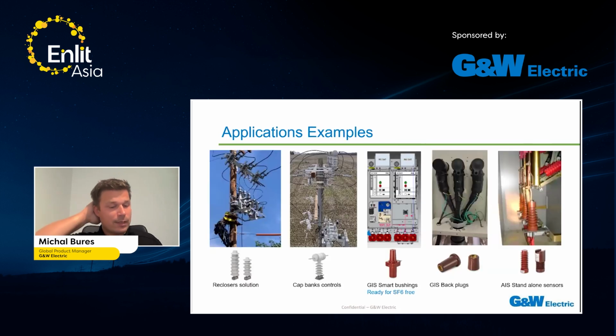Here we have a couple of examples where the sensors can be installed, just to give you a better image of the typical installation. For outdoor sensors, I should definitely mention the recloser solution, then the cap bank controls. For the indoor, GIS smart bushing installation in the GIS for the switchgear for ring main units. And we already have the SF6 solution. We also have backplugs for the cable connectors. And then for the air insulated switchgear, we have standalone sensors.